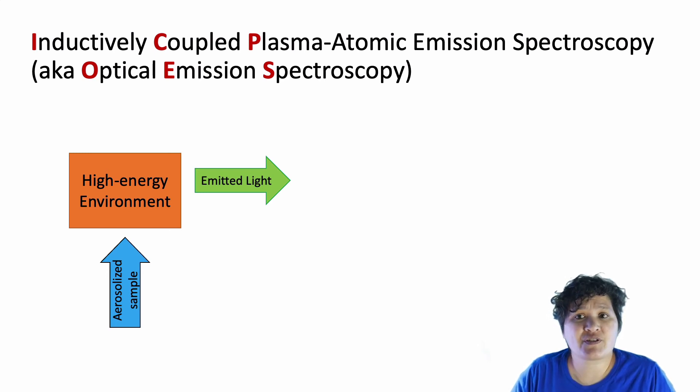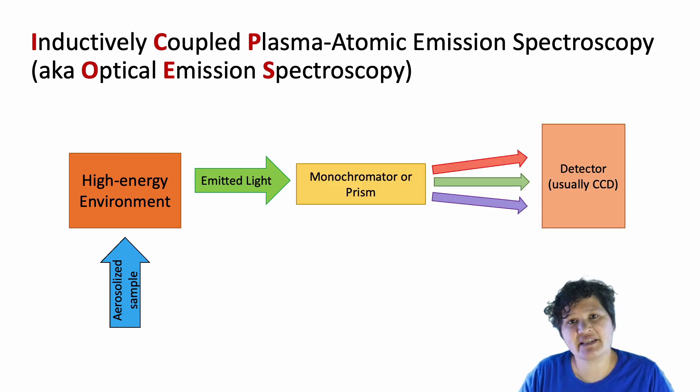So, here's the first obvious difference. The last instrument measured absorbance. Well, this one measures emission. Again, we have the monochrometer next, followed by a detector, which this time is a CCD. And the reason that it uses a CCD rather than a PMT is that that allows the instrument to collect many different wavelengths at once. But other than that, it does look very similar to what we saw in the AA.